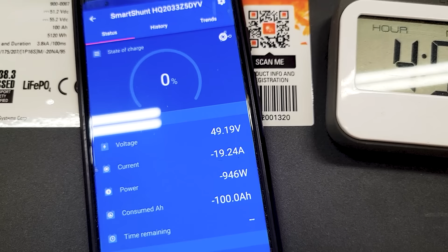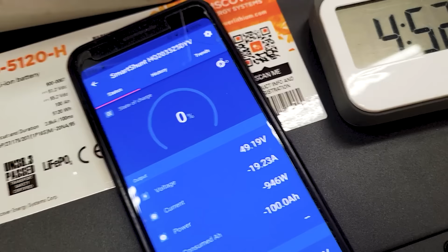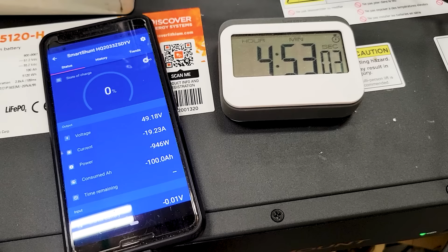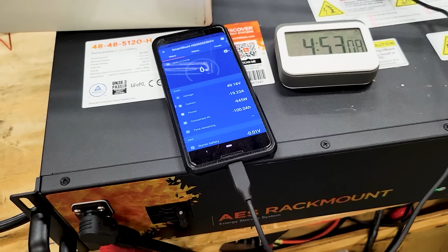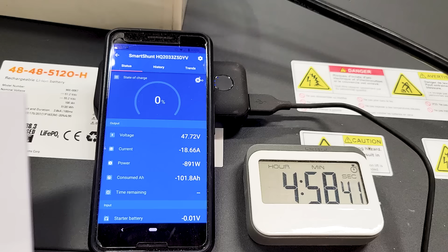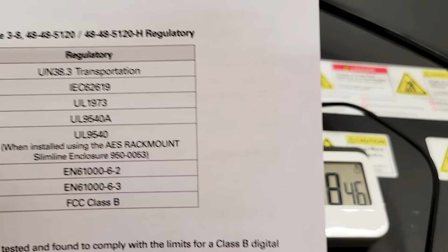And if we check out the status, we're at 0%, 49.2 volts, still discharging, a little under 20 amps at this point. It was over 20 amps until just a few minutes ago when we dropped down below 50 volts. So it should be done in just another few minutes. And I'll sit here and watch that so that we can capture it on camera. And by the way, since we're looking through the manual, this shows the regulatory information. So we can see the different UL classifications for this battery.